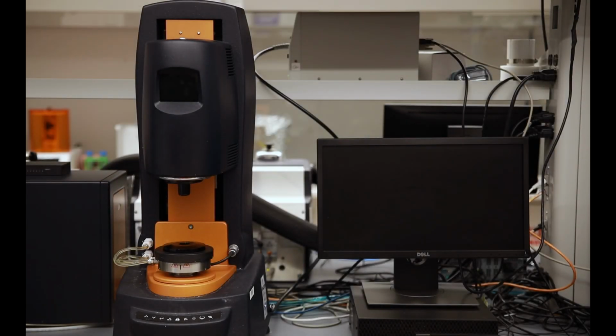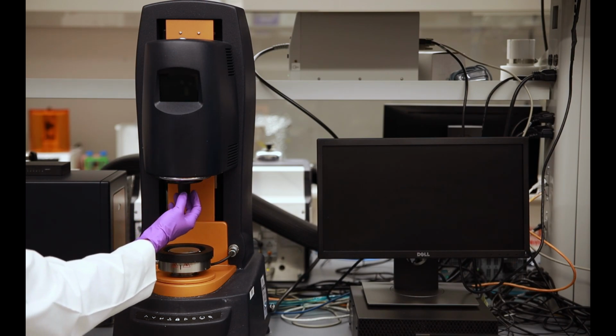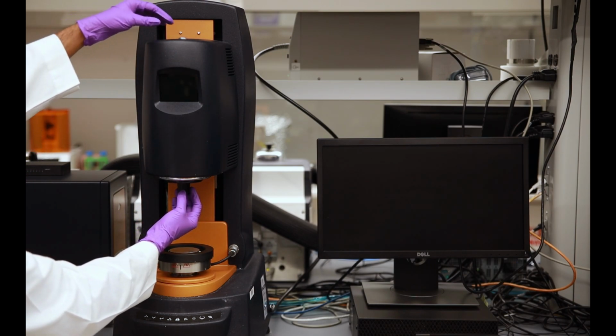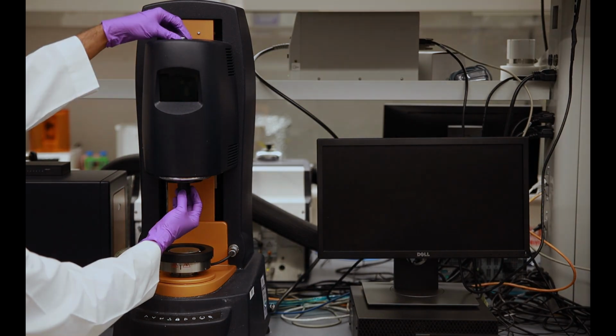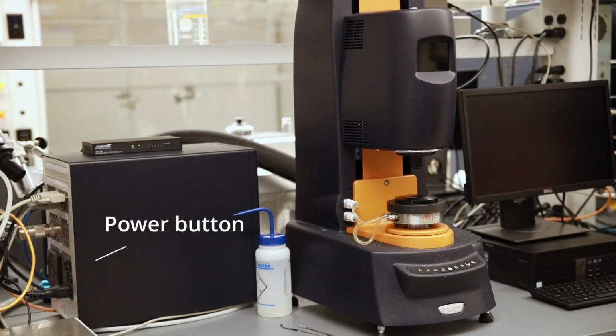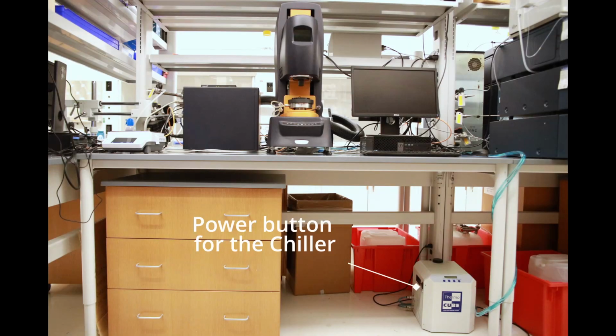Before powering on the equipment, remove the bottom cover plates, hold the top cover plate, and unscrew the down rod from the top. Turn on the equipment by pressing the power button. Now the display on the rheometer will be turned on. Turn on the chiller below the equipment down here.